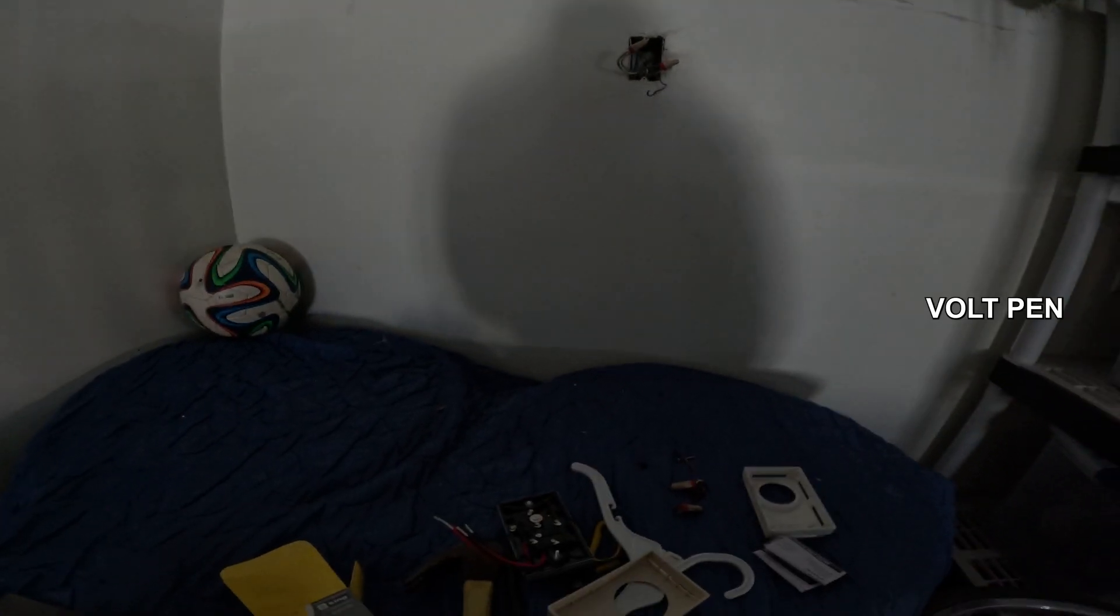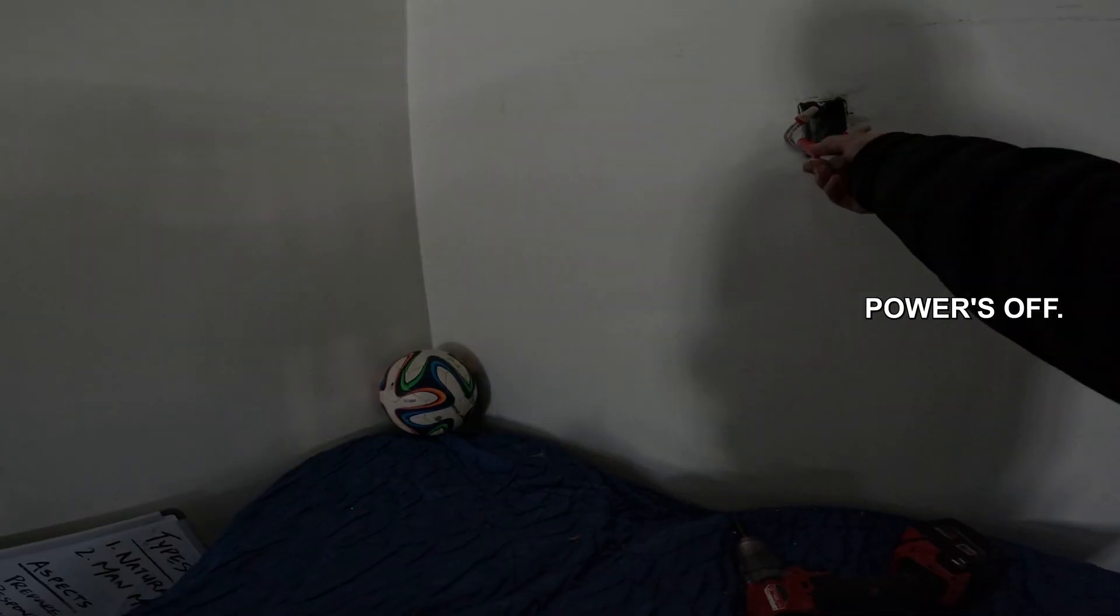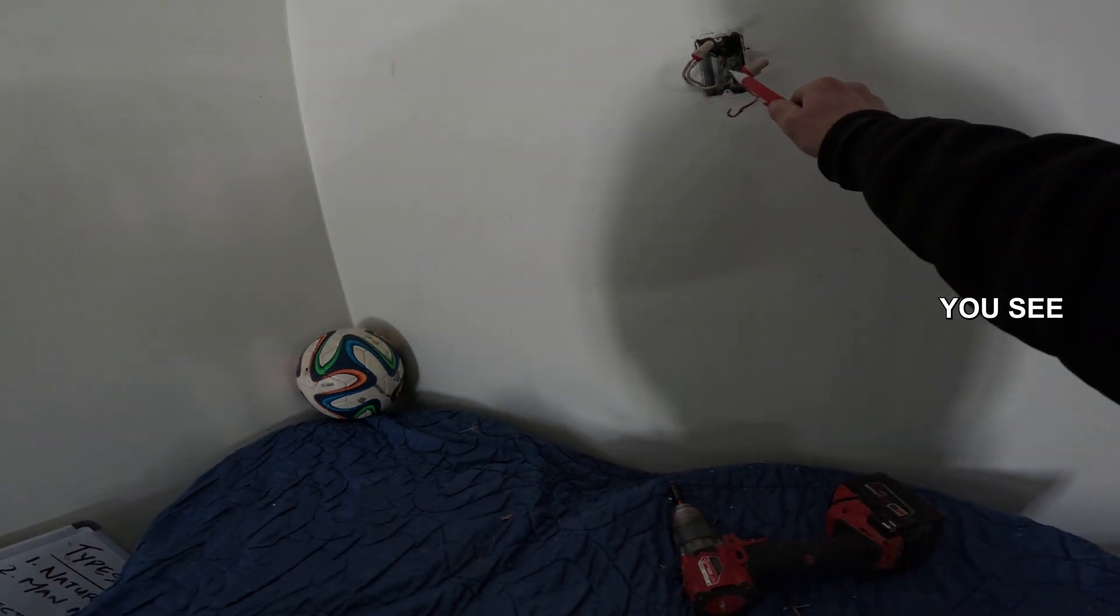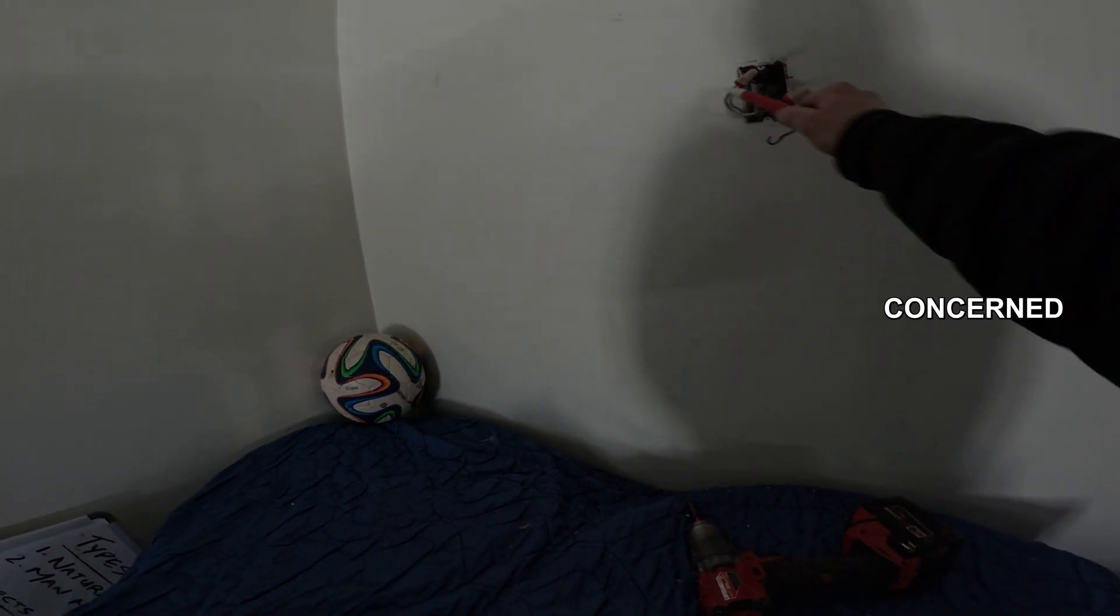I'm going to take my volt pen and just verify power's off. You'll see that it lights up but it doesn't stay on. When I touch it and you see a little red flicker, that's nothing to be concerned about. This tells me there's no power on there.